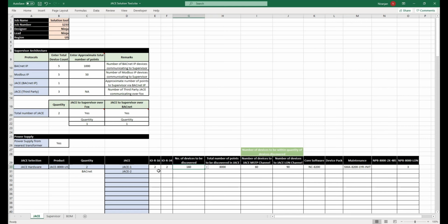Let's say I do the same to the BACnet controller here. I'm not going to select any of the IO modules for these ones. I'm just going to say I have almost 180 BACnet MSTP controllers coming in, and the number of LAN controllers that can be selected is 30. So it's going to select two of these and one of these. One single module can have two ports of RS-485, which gives you 30 per channel, which is almost 180 with inbound RS-485 considered.